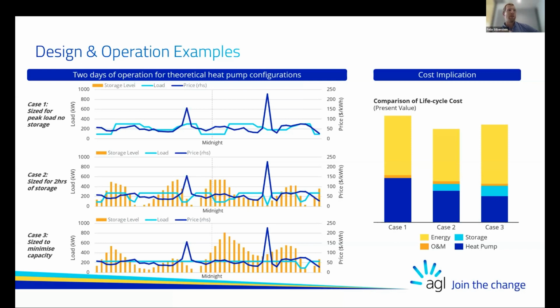At the other end of the spectrum, in case three, we're looking at minimizing the size of the heat pump. What's your load, and how low can we go to meet demand in all intervals, with enough storage so that our daytime load, or whenever it comes through, maybe morning or evening, is covered by operation in other intervals. That means you need to run base load flat out, and again you've got limited flexibility in terms of responding to price signals or whatever you're optimizing around, meaning a higher energy cost or not achieving another goal.